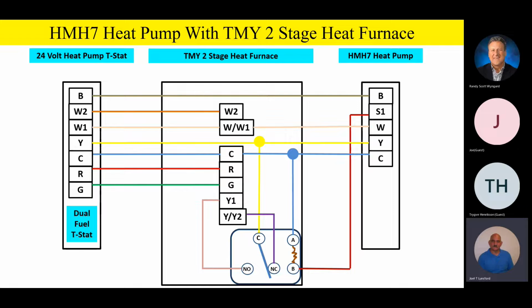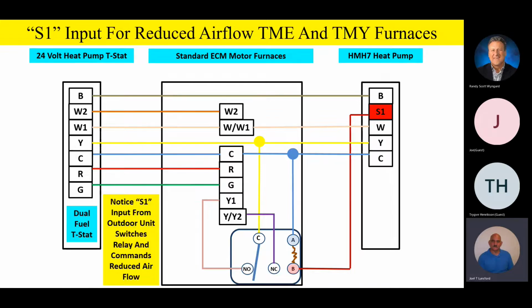Now, team, let's go ahead and look at an animation real quick, and let's energize that S1 output. And we see that S1 output, again, it's going to switch that relay, and it's going to switch from high-speed cooling to low-speed cooling, from Y2 to Y1. If we have a reduction in capacity outside, we'll switch that airflow. But please remember, team, again, because it's a standard ECM motor furnace, both TME and TMY are both standard ECM motor furnaces. We find that if we do have a defrost call and we have a higher speed command, it'll always switch to that highest speed command on that motor that it's receiving.